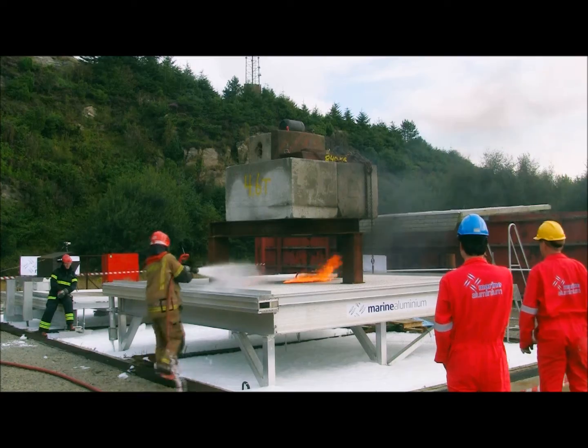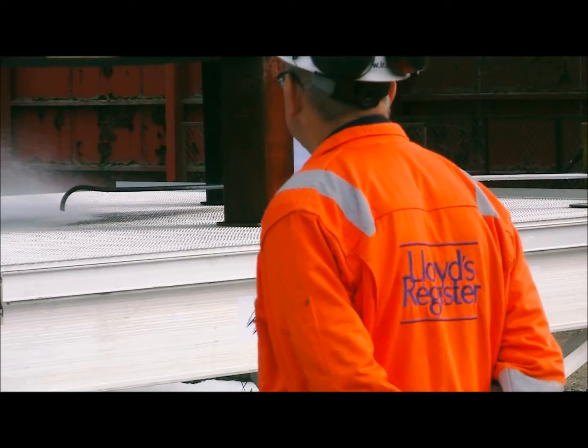About 90 to 95% of the fuel, at 13 litres per minute, is drained to the gutter. The lack of oxygen under the surface prevents the fuel from burning. A small fire is mainly fuel on the surface.